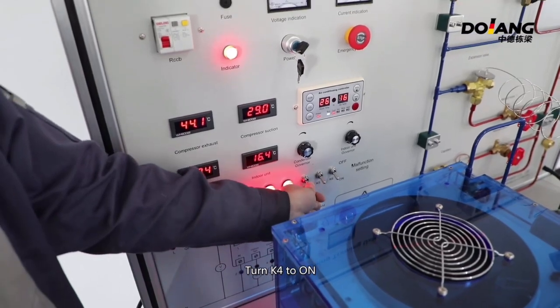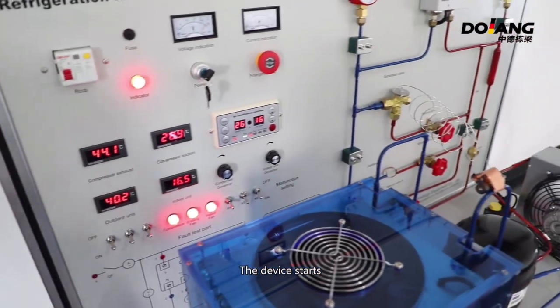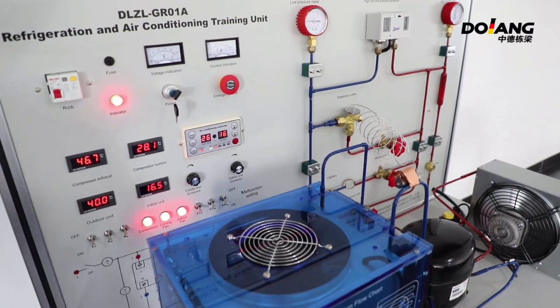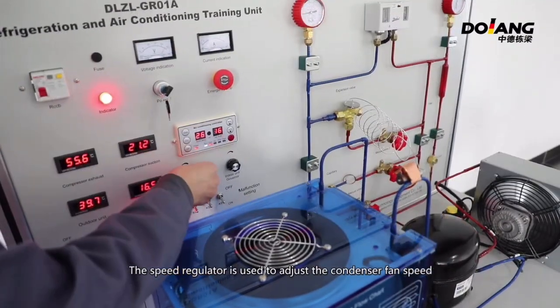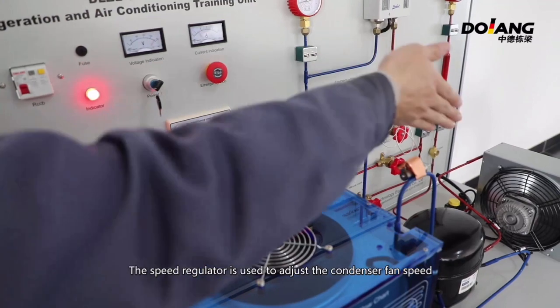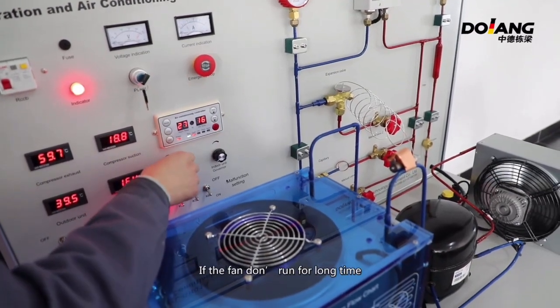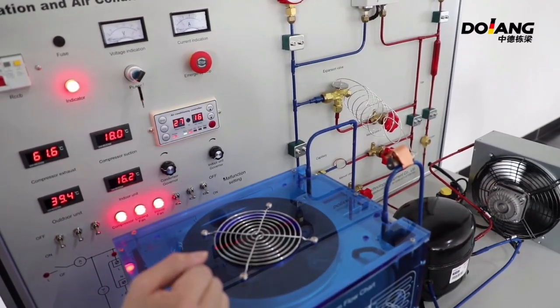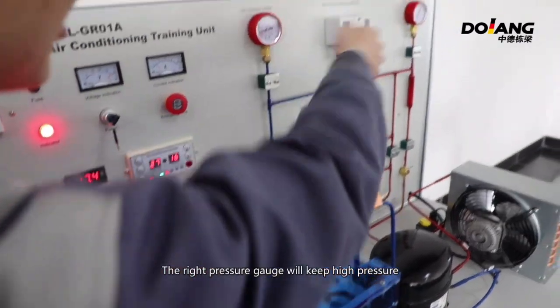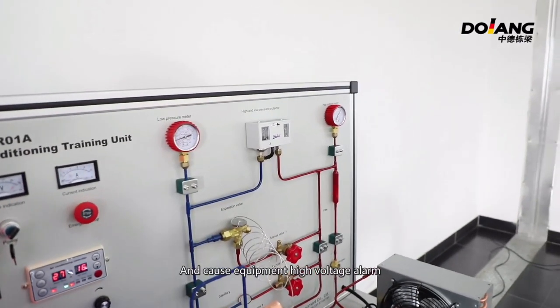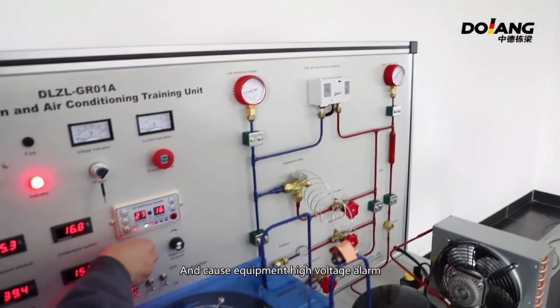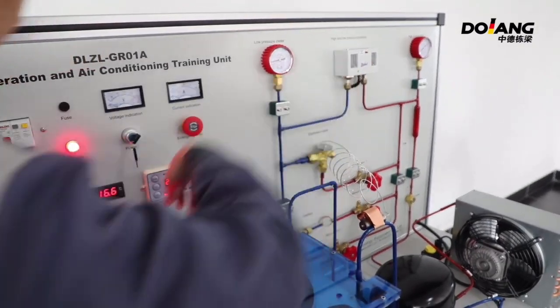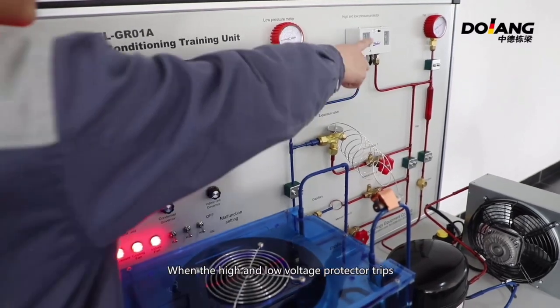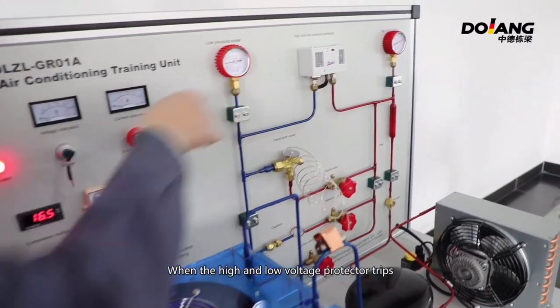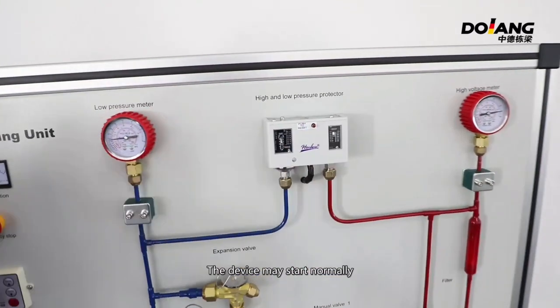Turn K4 to on. The device starts. The speed regulator is used to adjust the condenser fan speed. If the fan doesn't run for a long time, the right pressure gauge will keep high pressure and cause the equipment high voltage alarm. When the high and low voltage protector trips, may press the reset button. The device may start normally.